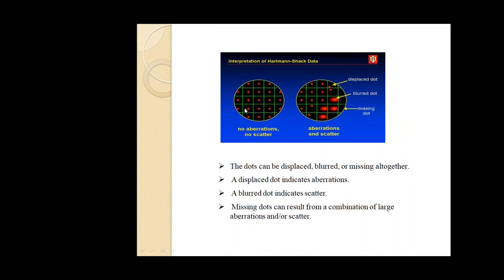In the interpretation of Hartmann-Shack data, regular dots indicate no aberration or scattering. Displaced spots indicate aberration, blurred spots indicate scattering, and missing spots result from a combination of large aberration or scatter. So a dot can be displaced, blurred, or missing altogether. The displaced dot indicates aberration, the blurred dot indicates scattering, and the missing dot results from combined large aberration or scatter.